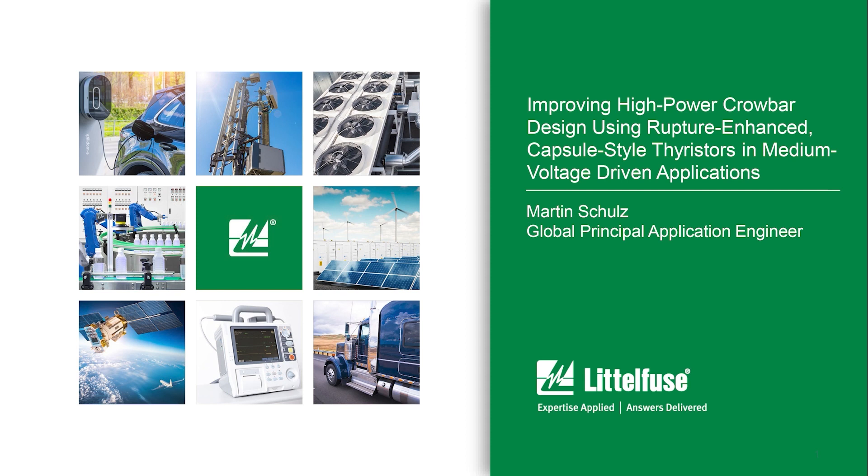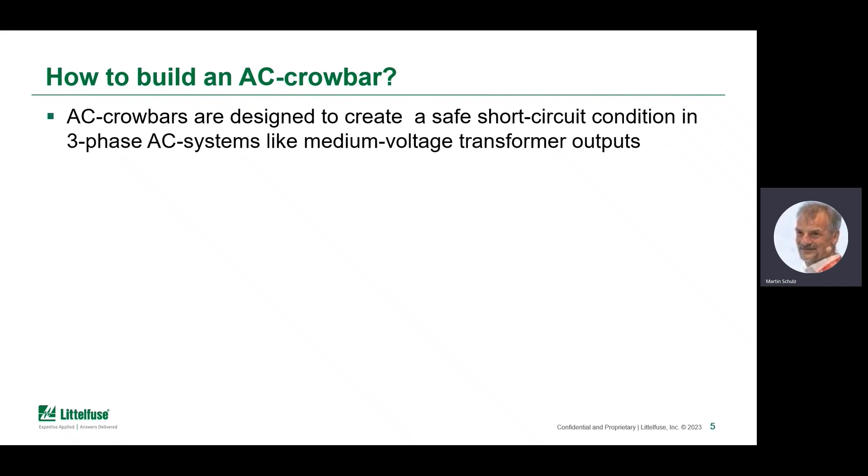Welcome to the presentation about how crowbars can be designed using rupture-enhanced, capsule-style thyristor devices, particularly targeting medium-voltage-driven applications. Medium-voltage means we're talking about AC applications — how to build an AC crowbar, an entity designed to create a safe short-circuit condition in order to blow a superordinate fuse or give some time for mechanical switchgear to open.